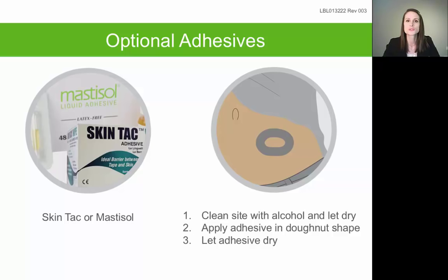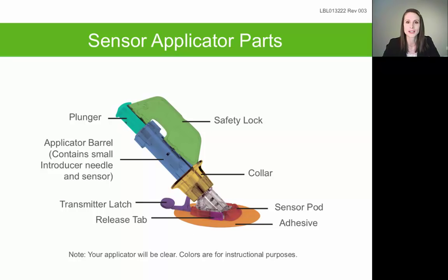You have the option of using two types of medical adhesive on your skin prior to sensor placement. The two brands we recommend are Mastisol and Skin Tac. If you choose to use these, apply them in a donut fashion — an oblong oval shape, leaving the center exposed without any overlying glue — so when you place the sensor pod on top, the needle punctures through your skin and not through the glue. Let the Mastisol or Skin Tac dry for about 30 seconds to become sticky and tacky before placing the sensor pod on top.